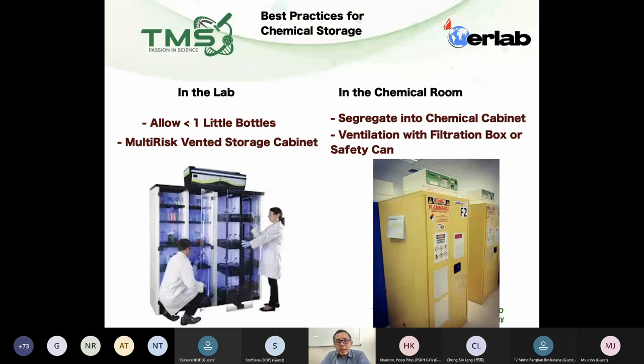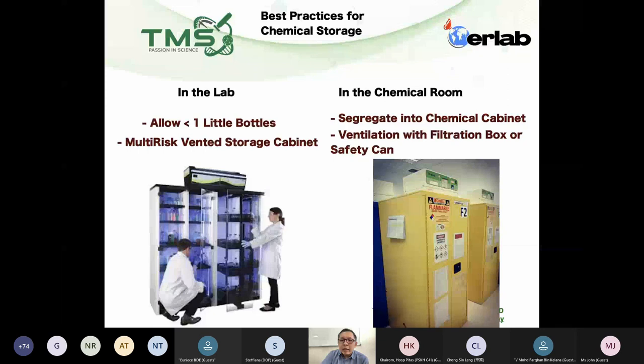In the chemical room, you typically buy chemicals in large quantities due to budget, so they go into your inventory. In that situation, I recommend storing them in flammable cabinets and acid cabinets. For the working laboratory, you normally have multiple types of chemicals but in smaller quantities — one liter or less — and those can go into a vented multi-risk storage cabinet.